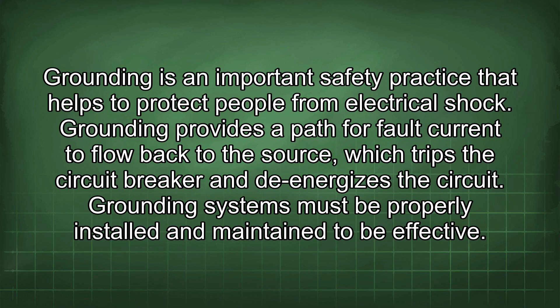Grounding is an important safety practice that helps protect people from electrical shock. It provides a path for fault current to flow back to the source, tripping the circuit breaker and de-energizing the circuit. Grounding systems must be properly installed and maintained to be effective, and the NEC contains detailed requirements for grounding electrical systems.